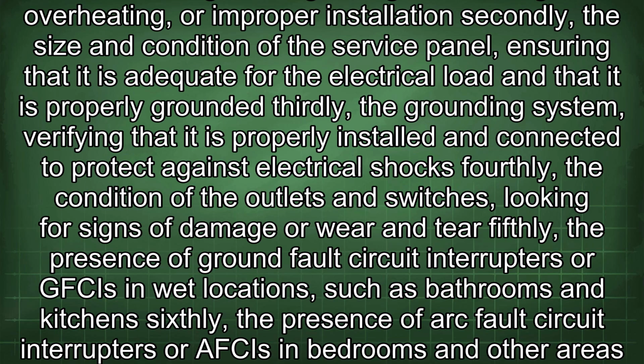Firstly, the condition of the wiring, looking for signs of damage, overheating, or improper installation. Secondly, the size and condition of the service panel, ensuring that it is adequate for the electrical load and that it is properly grounded. Thirdly, the grounding system, verifying that it is properly installed and connected to protect against electrical shocks. Fourthly, the condition of the outlets and switches, looking for signs of damage or wear and tear. Fifthly, the presence of ground fault circuit interrupters, or GFCIs, in wet locations, such as bathrooms and kitchens. Sixthly, the presence of arc fault circuit interrupters, or AFCIs, in bedrooms and other areas to protect against electrical fires. And seventhly, the overall compliance of the electrical system with the NEC and local electrical codes.